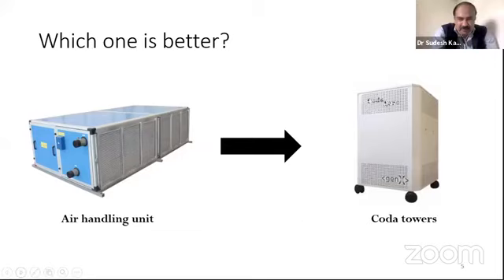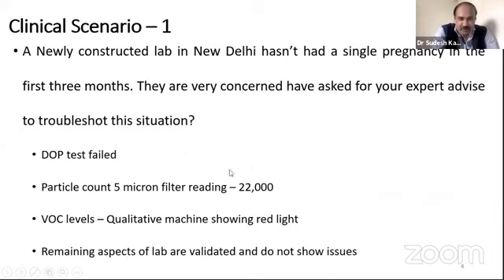Before I come to the previous slide, where you mentioned particulate count more than 22,000 and the DOP test failed, I think there is a problem with the HEPA filter. It's just a 3 months old, newly set up lab. So the first thing is to catch hold of those people: why is the DOP test failing? That means your HEPA filter is defective. That is my opinion.